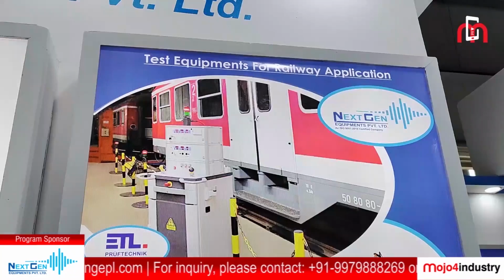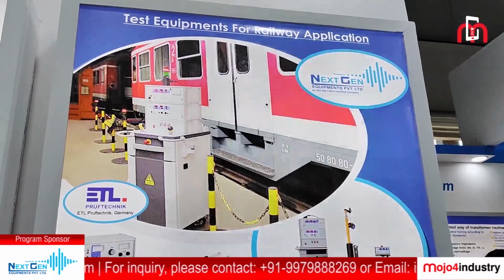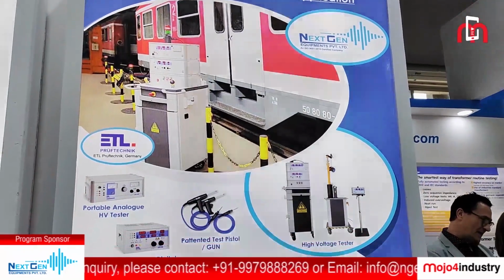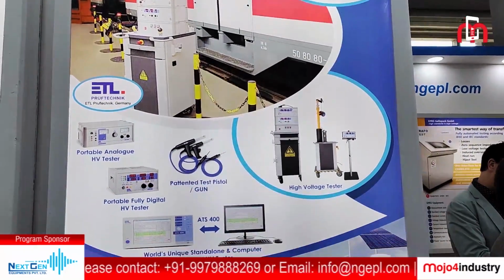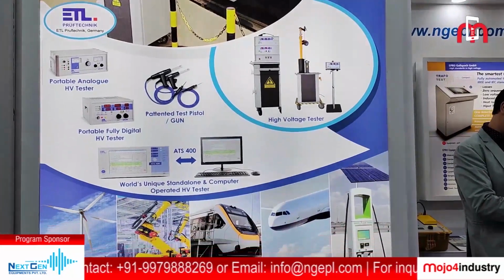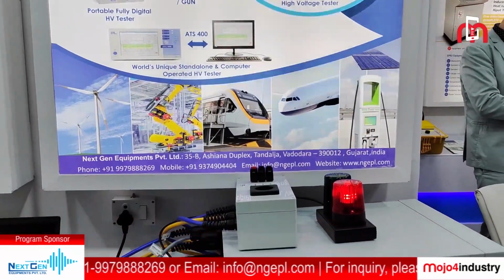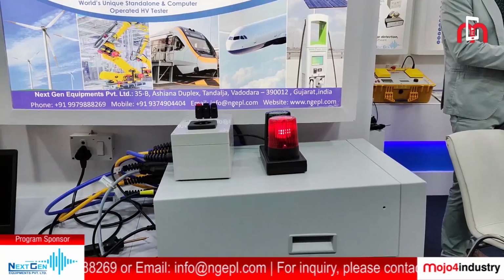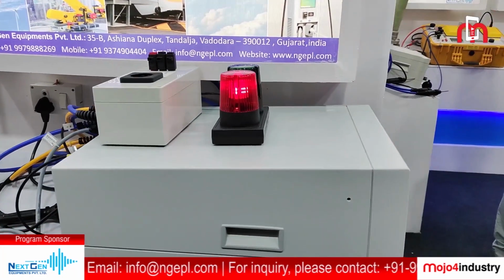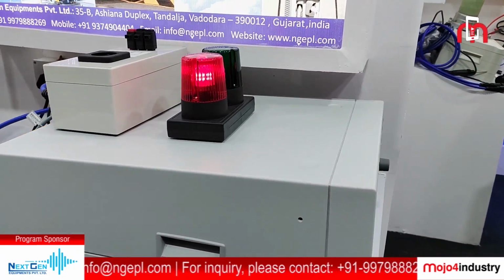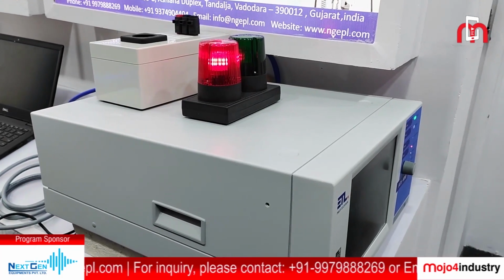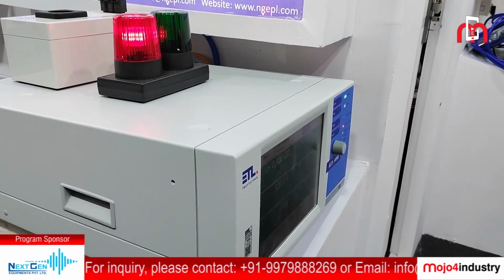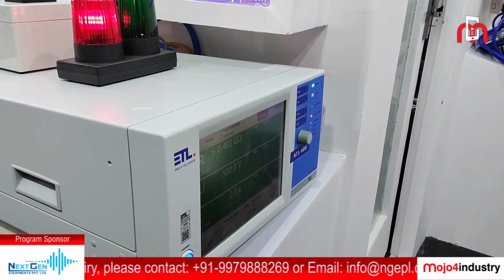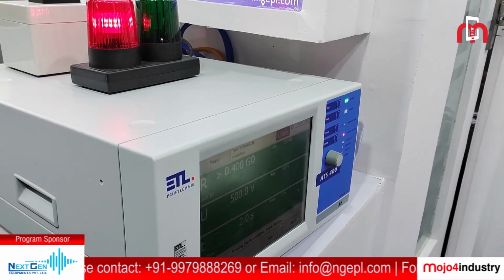Beginning with the earth continuity test, the isolation resistance test, high voltage AC, high voltage DC test, functional run test, line leakage test, and so on. All these products are manufactured in Germany at a high level of quality, with products sent all over the world.